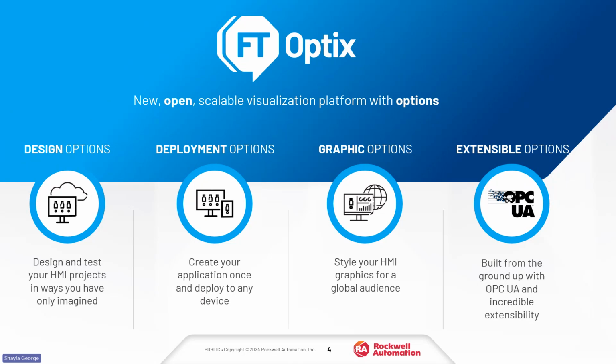But additionally, from a third-party standpoint, there are native third-party drivers inside of Optix that also give you the ability to communicate to those third-party devices. If there is a need to communicate to a third-party device that does not have a native driver inside of Optix, Optix does support OPC-UA. It's built completely on top of the OPC-UA specs. So Optix can serve as a server or a client to serve that data and allow for that machine-to-machine communication, as well as the MQTT protocol. So if that is a protocol that's needed to allow for the flow of data, Optix does support that.